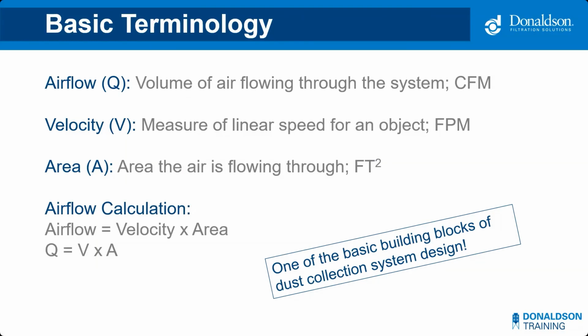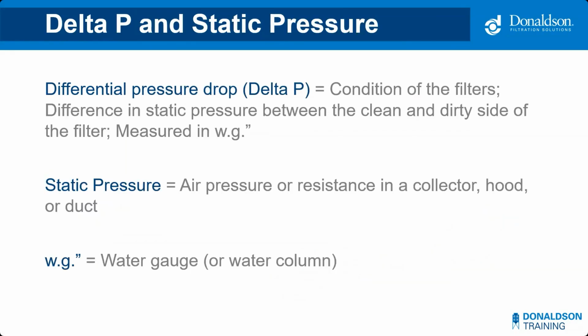You really want to have the ideal airflow for moving the particulate through the dust collection. You don't want to have too much or too little, so this is a very important formula to understand. And then we have pressure drop, or delta P, which essentially tells us the condition of the filters as it loads with dust. The difference in static pressure or resistance between the clean side and the dirty side of the filter. It's measured in inches of water gauge or water column.